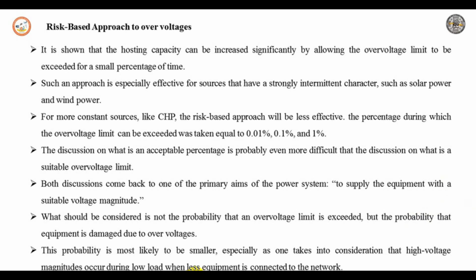It is shown that the hosting capacity can be increased significantly by allowing the over voltage limit to be exceeded for a small percentage of time. Such an approach is especially effective for sources having a strongly intermittent character, such as solar power and wind power. For a more constant source like CHP, a risk-based approach will be less effective. The percentage of time during which the over voltage limit can be exceeded was taken equal to 0.01%, 0.1% and 1%. The discussion on what is an acceptable percentage is probably even more difficult than the discussion on what is a suitable over voltage limit. Both discussions come back to one primary aim of the power system: to supply the equipment with suitable voltage magnitude. The risk-based approach should be discussed.